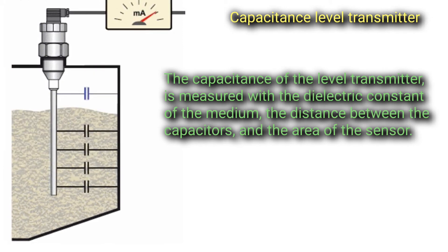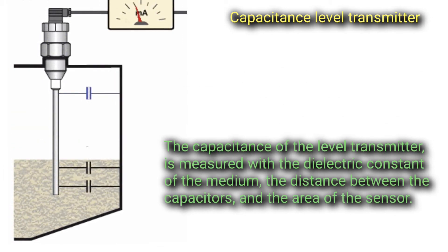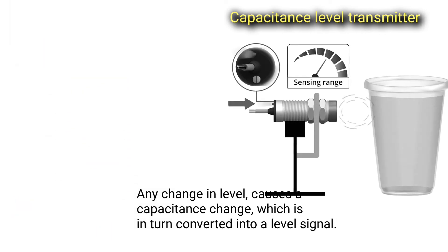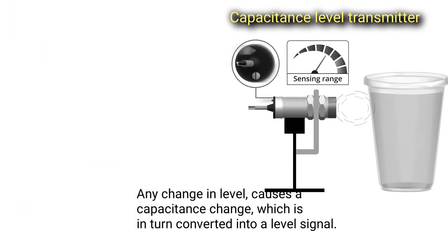The capacitance of the level transmitter is measured with the dielectric constant of the medium, the distance between the capacitors, and the area of the sensor. Any change in level causes a capacitance change which is in turn converted into a level signal.